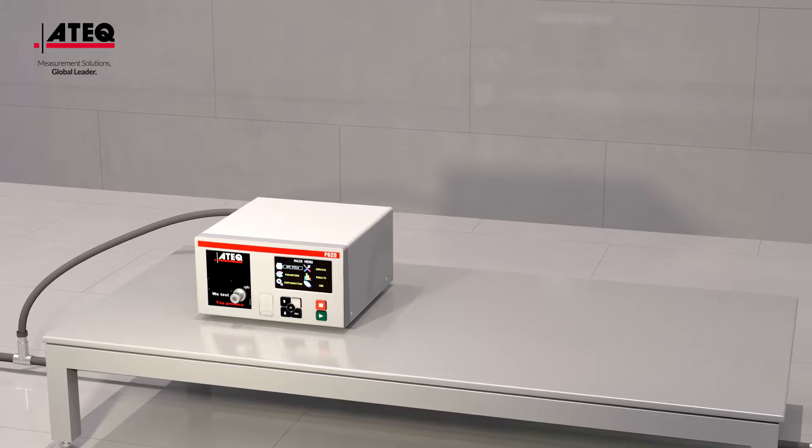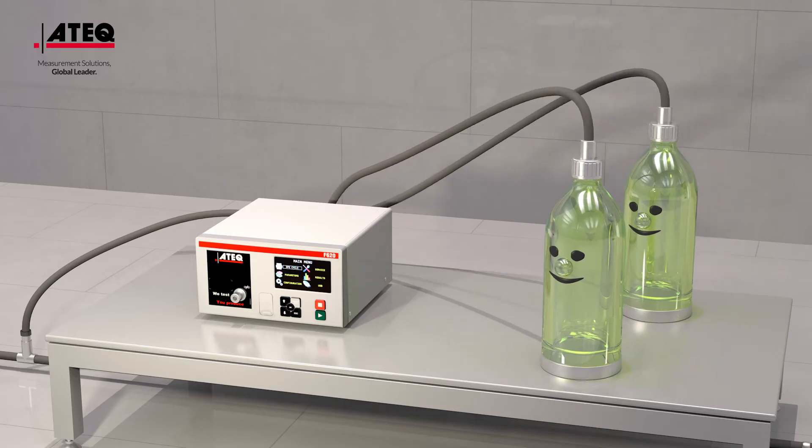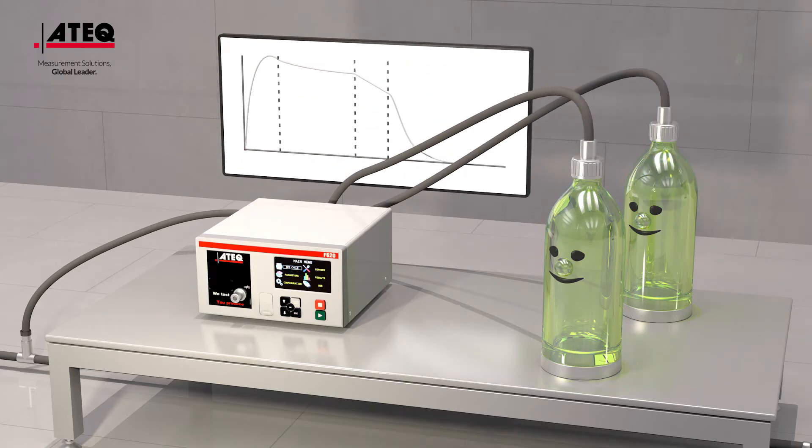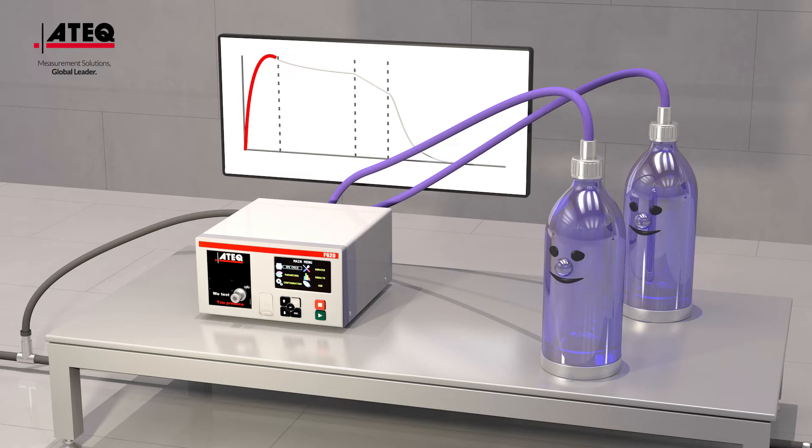The principle is simple. A part with a potential leak and a sealed reference piece are filled with pressurized air. The filling time is followed by a stabilization time used to eliminate the micro pressure variations that disturb the measurement.